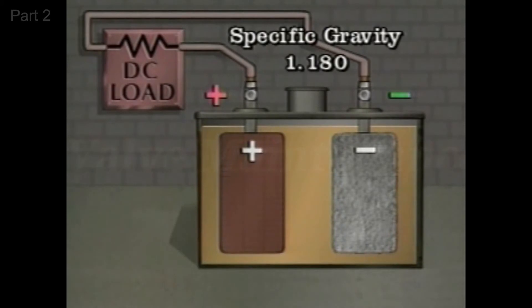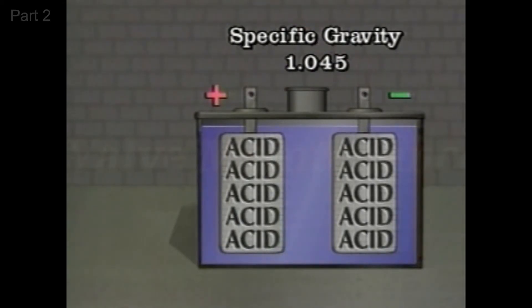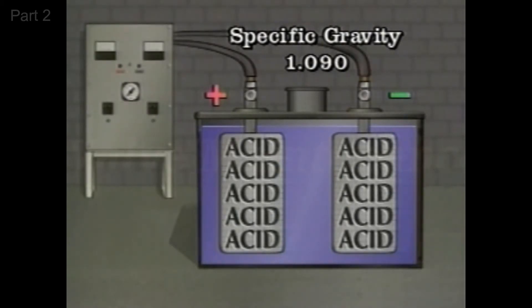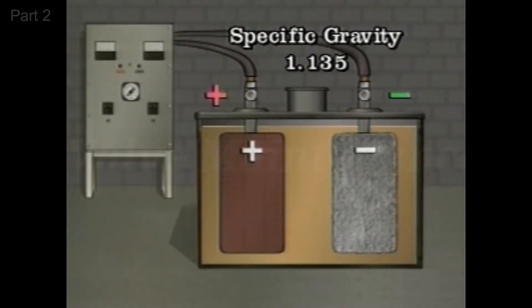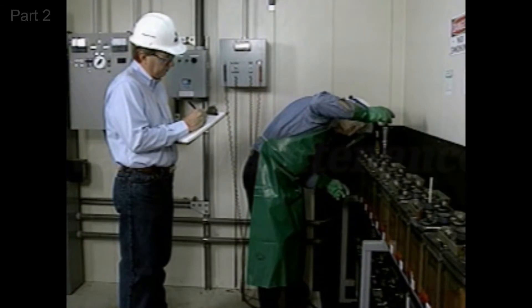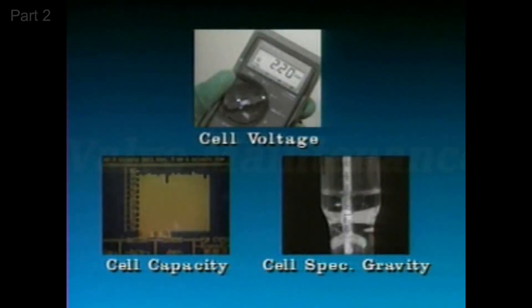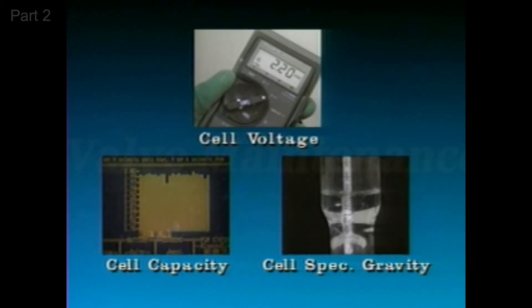As the cell discharges, the specific gravity of the electrolyte decreases because sulfuric acid leaves the electrolyte and combines with the lead in the plates of the cell. When the cell is recharged, the specific gravity increases because sulfuric acid is driven off the plates and back into the electrolyte. So the specific gravity of a cell provides another indication of a battery state of charge and its ability to provide the required backup power when it's needed. In-service cell voltage, capacity, and specific gravity are all indicators of a battery state of charge and its ability to provide backup power, and the value of each of these indicators is related to the value of the other two.